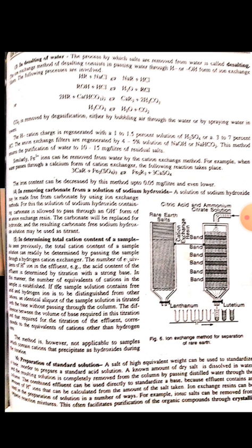Similarly, ferric ions can be removed from water by the cation exchange method. For example, when water passes through a calcium form of cation exchanger, the following reaction takes place in which the calcium ions combine with sulfate to form calcium sulfate and ferric ions enter the exchanger. The iron content can be decreased by this method up to 0.05 milligrams per liter.